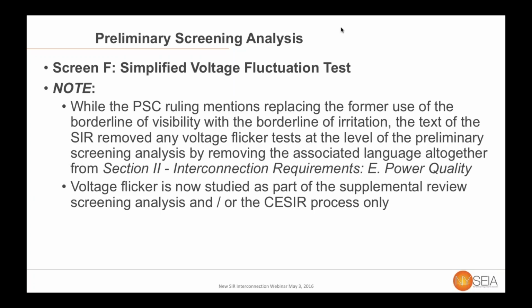The last thing to note about this, in the PSC ruling, if you have read it, you will have noticed that at one point they make reference to moving in the voltage flicker analysis from the borderline of visibility to the borderline of irritation, which is the higher level. This, however, has been removed entirely from Section 2. The language under the power quality section that used to reference flicker has now been removed, and voltage flicker is now something that will be considered and analyzed within the context of supplemental screening, the supplemental review, or the CESIR process.